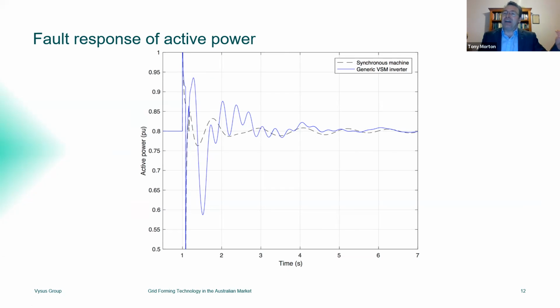You'll see there's quite a bit of oscillation here, and we can understand this because the generic grid forming converter we're using in this case doesn't actually have a power system stabilizer in it, whereas the synchronous machine has. And what this points to is that the grid forming inverter is doing the job in giving us the stable power flow, but it's a bit wobbly because we've actually done away with the traditional thing that we know synchronous machines need to have, which is stabilizers to provide damping in the power system. And this does point to the desirability of having that same damping contribution put into the control system for the grid forming converter. And there are a number of ways we can look at doing that. That's something we're looking at the moment.